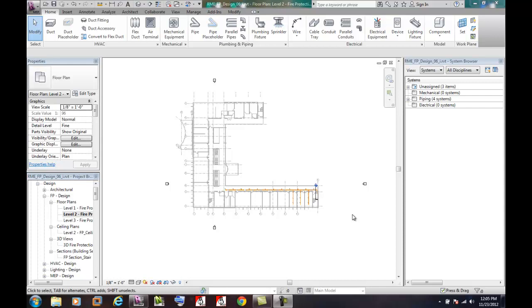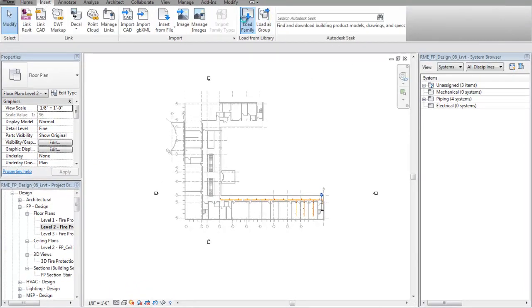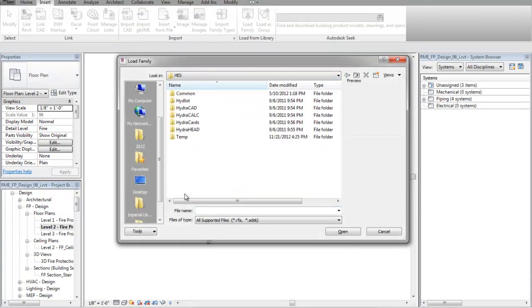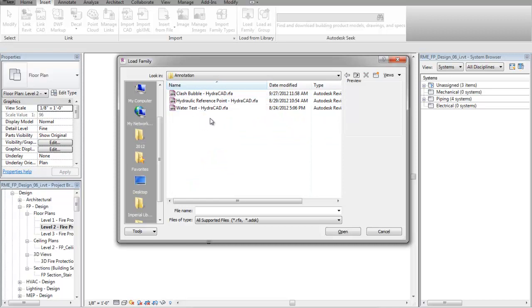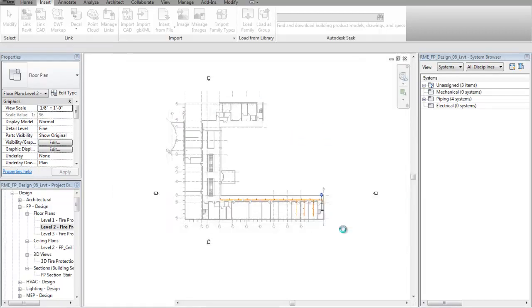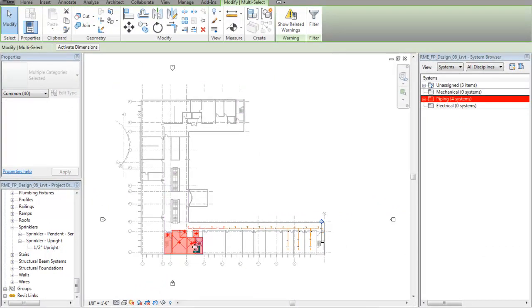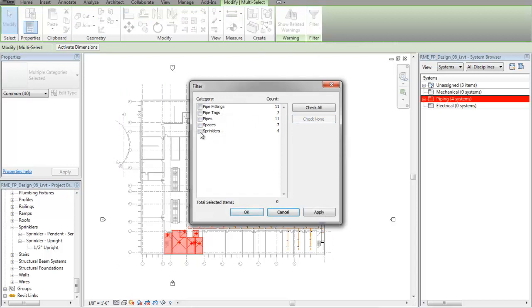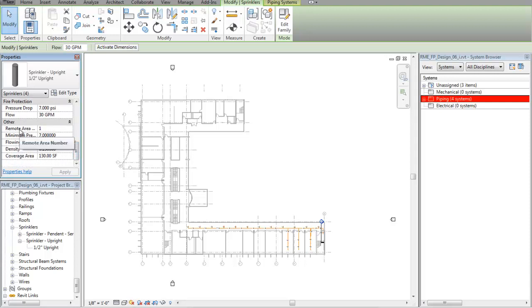There are a few things we'll need to do prior to running the calculations. First, we need to load the required annotation families. HydraCalc for Revit will add some additional properties to the sprinkler head families during setup. Operating sprinklers within the design area need to be selected. Area number, minimum pressure, whether these sprinklers are flowing for this set of calculations, NFPA required density, and coverage area all need to be entered.